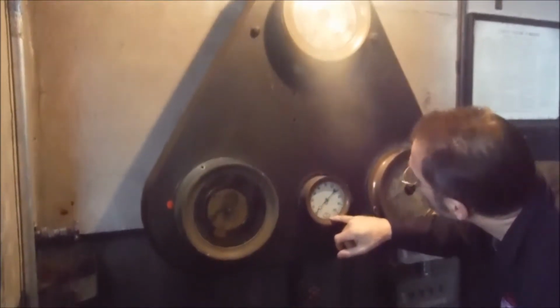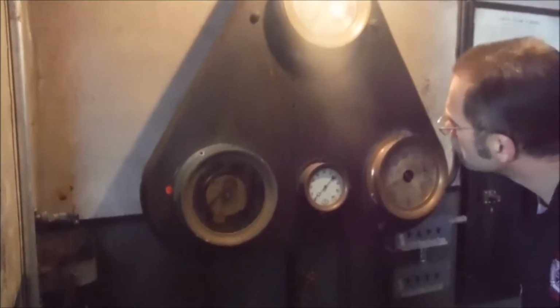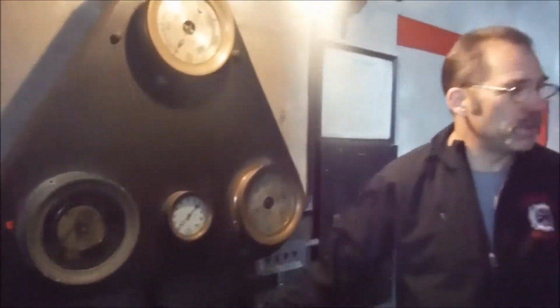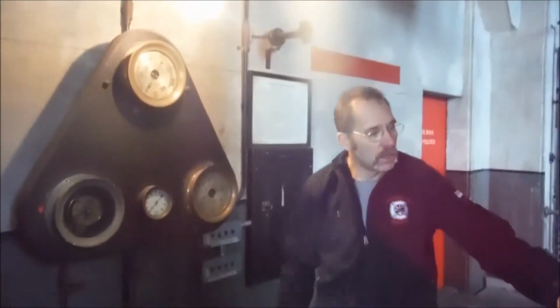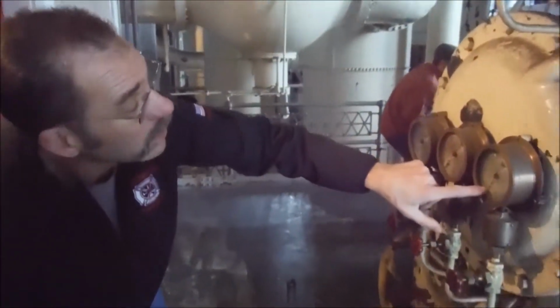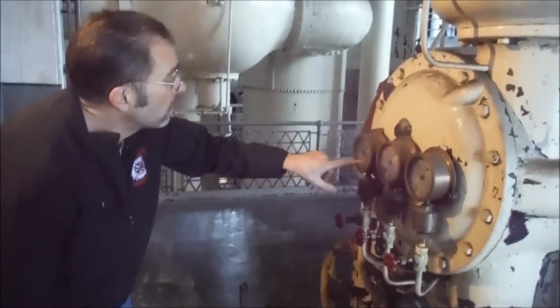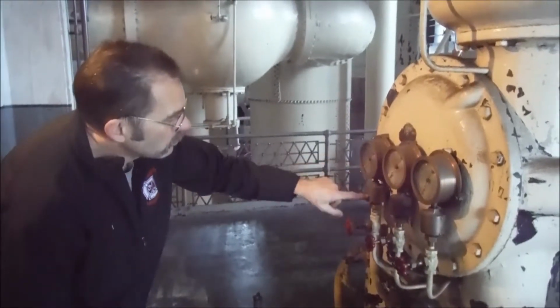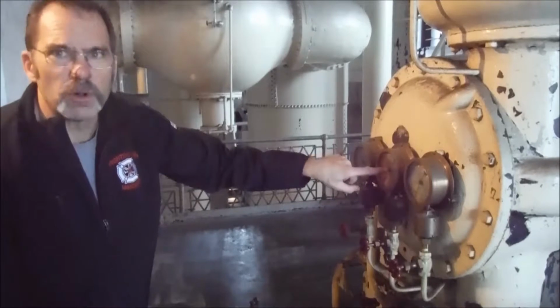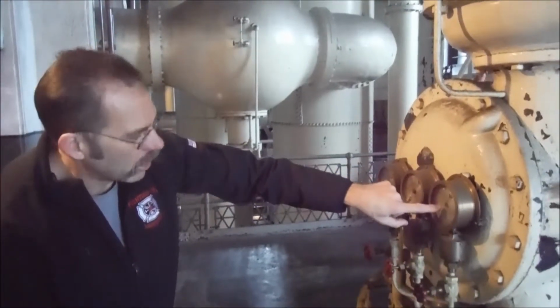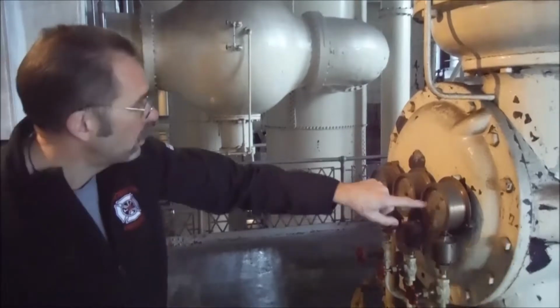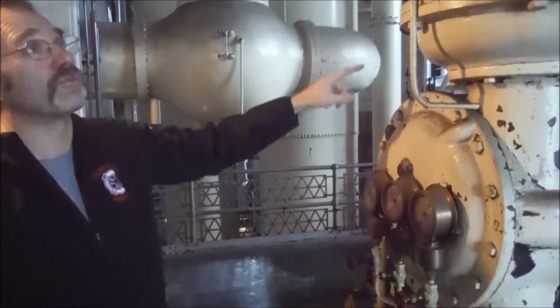150 psi into that first stage is a big load. This is another pressure gauge, but I assume it's pressure 0 to 100, lube oil pressure or something like that? Probably oil pressure, sure. But the guy in charge of keeping this thing operating safely would be standing here. What do we got here? So we got a hydraulic gear pressure gauge, bearing, and water pressure. So bearings, that would probably be oil pressure to the turbine bearings, and hydraulic gear pressure is probably oil pressure to the hydraulic control system.